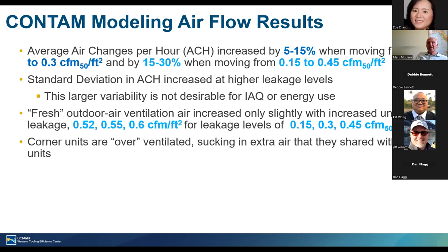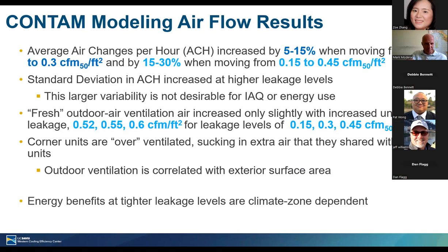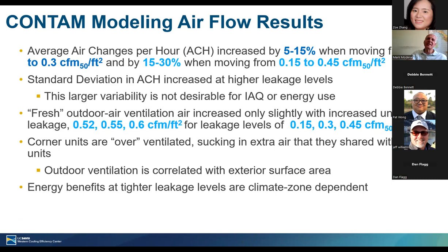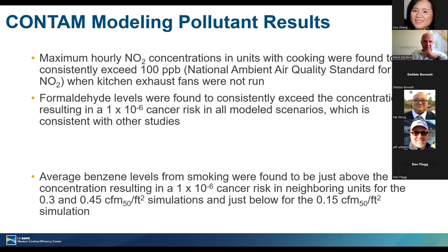Not surprisingly, corner units are overventilated, sucking in extra outdoor air which they in turn share with interior units — not a big surprise given that corner unit surface area to outside is much larger. At the tightest leakage level, corner units have almost all their air coming from outdoors, while middle units have only about 30% of their air coming from outdoors. The variation in the fraction of outdoor air changes dramatically as you go to leakier buildings, and particularly for middle units, the fraction of outdoor air can range from nearly 0% to 60% in a leaky building.